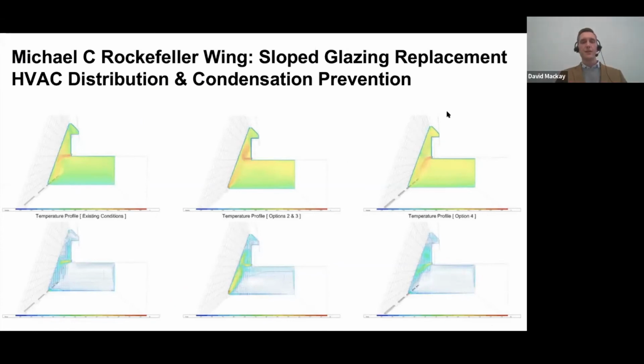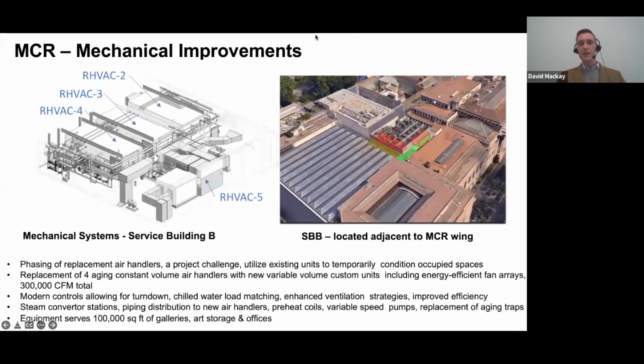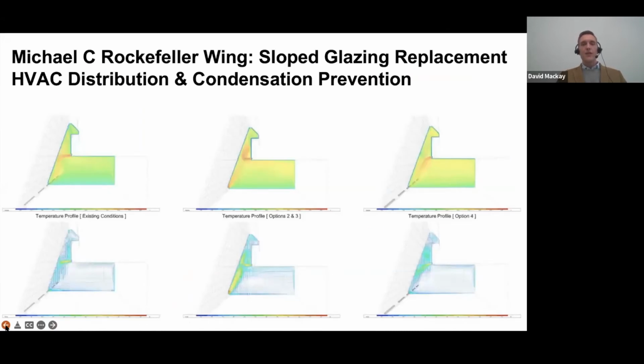Similar to what Henry was talking about with the convective loops changing within the glazing system when it's sloped—if you go back to that previous slide, please—we wanted to ensure our HVAC distribution would go along the entire sloped curtain wall. We only had two existing points to distribute air from, so we used computational fluid dynamics to look at different velocity and temperature profiles, and to see what we'd need for sizing of the system, the velocity of the air delivered, and the angle delivered, to make sure the glazing surface was a consistent temperature throughout that high elevation with the sloped condition.